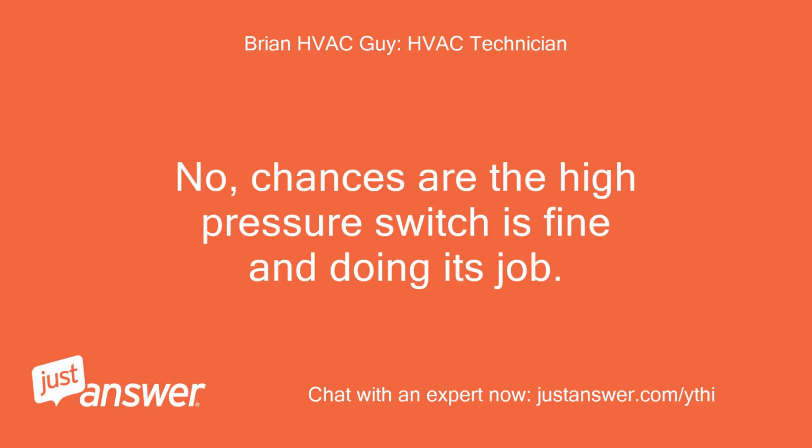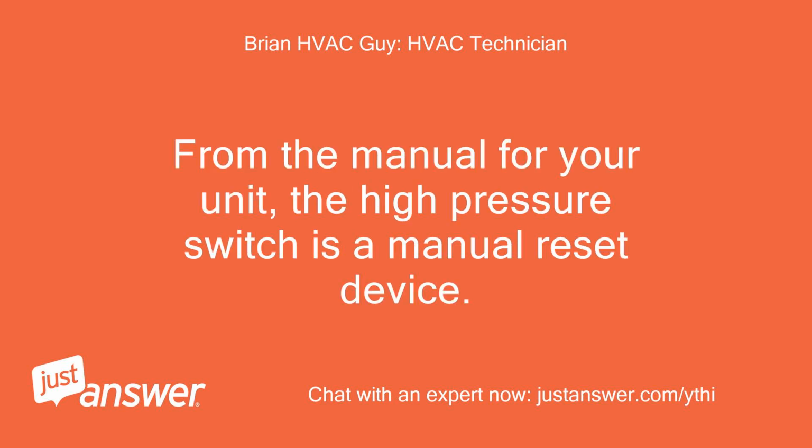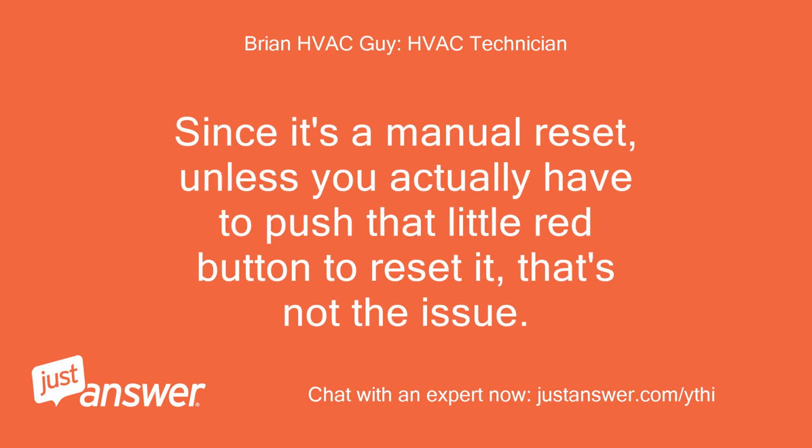No, chances are the high pressure switch is fine and doing its job. I think we are on separate pages here. From the manual for your unit, the high pressure switch is a manual reset device. There should be a little red button next to where the copper lines enter the outdoor unit. Since it's a manual reset, unless you actually have to push that little red button to reset it, that's not the issue.